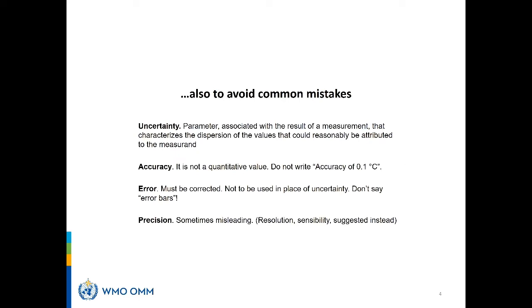For example, what is the uncertainty? We will see that there is a complete session on uncertainty. I think it's tomorrow. Accuracy is not a quantitative value. You will read so many data sheets of instruments that say the instrument has an accuracy of 0.1, of 10 pascal. It's wrong, because people don't like to say uncertainty. They think uncertainty is something bad, something to hide. It's a negative concept. It isn't. Accuracy is qualitative: it tells you how well I can be close to a true value. But please take a data sheet of your instrumentation, you will read accuracy somewhere. Error must be corrected.